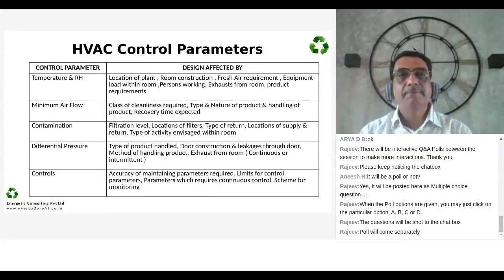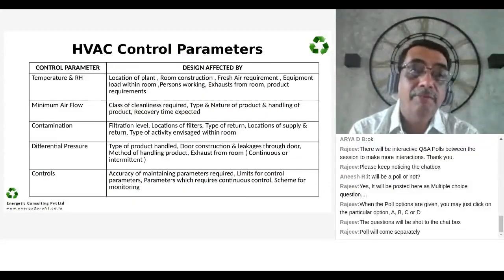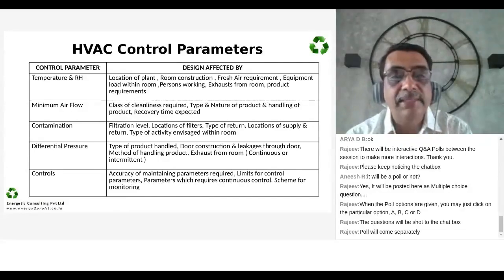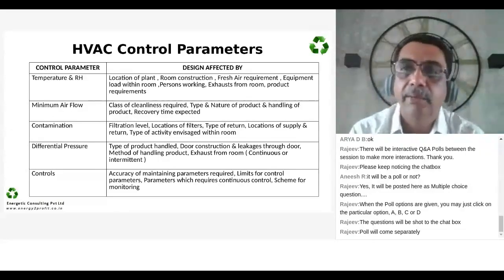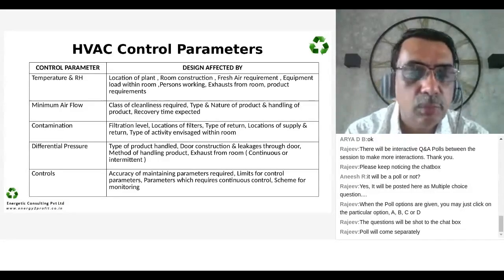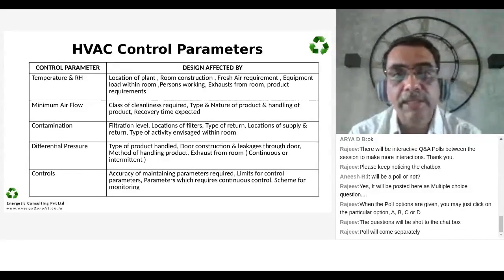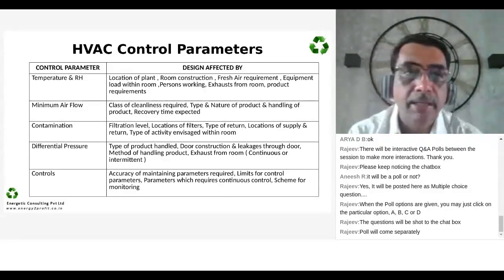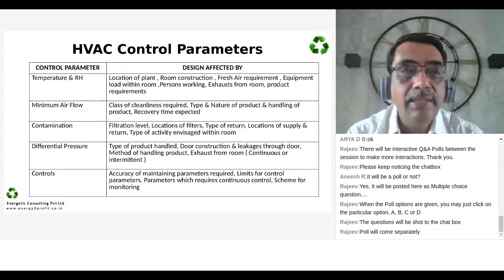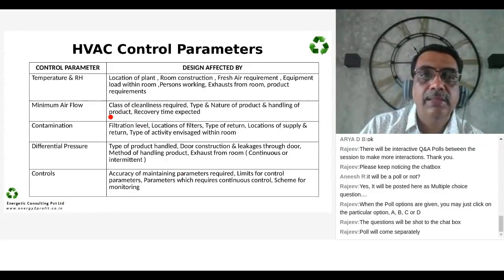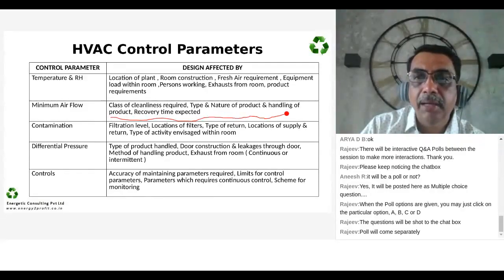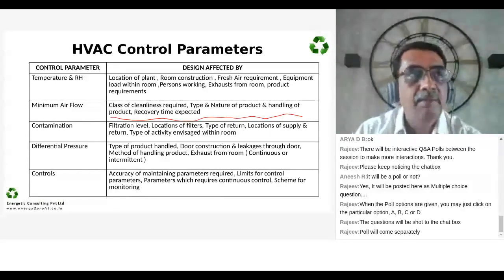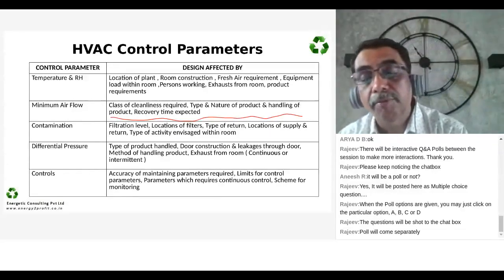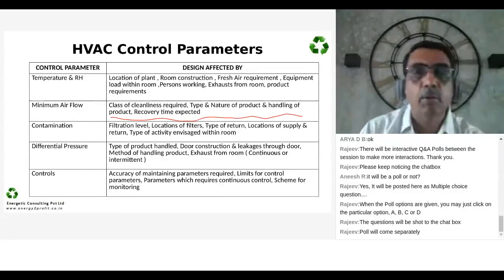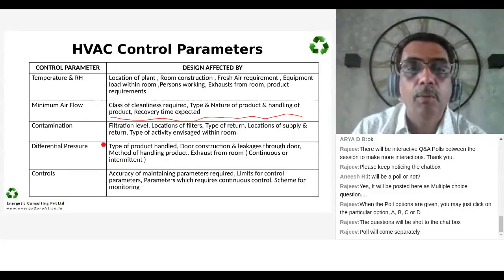So to summarize, what are we saying? HVAC control parameters: you have temperature and relative humidity. What affects it? Location of the plant, room construction, fresh air requirement, equipment load within the room, persons working, exhausts from the room, product requirements, and so on and so forth. Second is minimum airflow, that is, class of cleanliness, type and nature of product handled defines it, recovery time expected. Now this, I would like to just bring to your notice, are not comfort determinants. These are for industrial applications where air conditioning is a fundamental need for a product quality perspective and not comfort only. Comfort is a consideration, but not the only consideration.